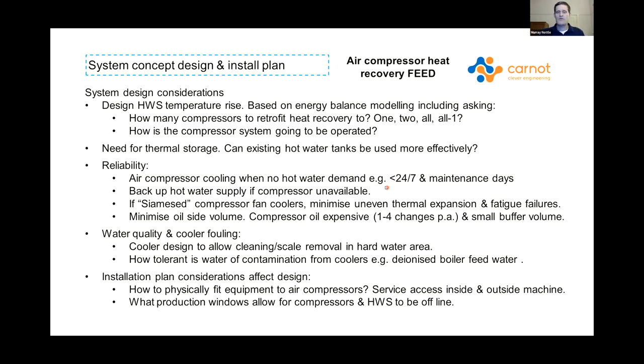What happens when you're running the air compressors, but you're not running your hot water? Air compressors will run all weekend and all week, more often than not, because they're supporting a lot of different services and they don't get turned off. But if you're only a 5-day a week production operation, what happens on the weekend when you've got no hot water demand available? What does the air compressor do? Similarly, what happens if one of your air compressors is down for servicing, say you've only fitted heat recovery to one of the compressors, when it's getting serviced 3 or 4 times a year, as they will, what happens with your heat supply system then? So you do have to have an alternate source of hot water for that backup scenario.